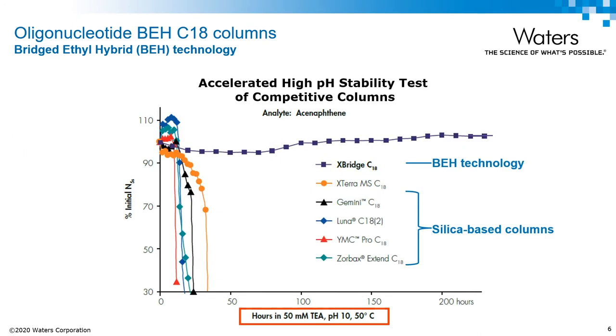This figure demonstrates the stability of the BEH particles under high pH. An accelerated high pH test was done to compare BEH technology to silica-based columns. Columns were equilibrated with TEA-containing mobile phase buffered to pH 10 at 50°C for the number of hours indicated at the bottom of the figure. During this time, columns were periodically flushed with water and methanol, and efficiency was tested using a hydrocarbon analyte. The lifetime of the BEH columns exceeded the best silica-based columns by an order of magnitude.